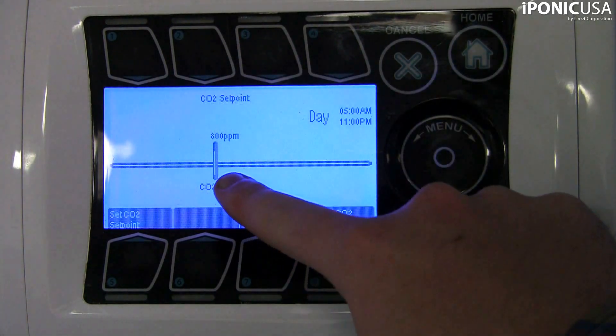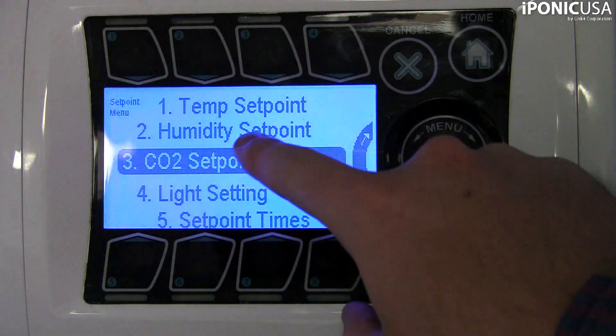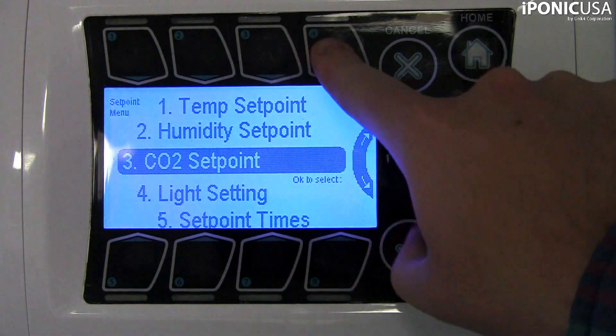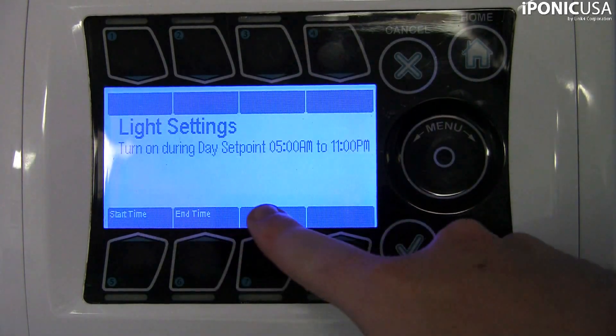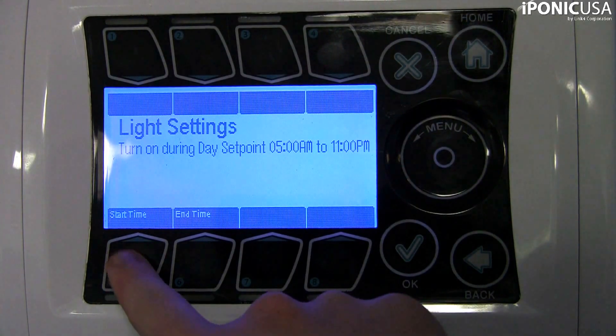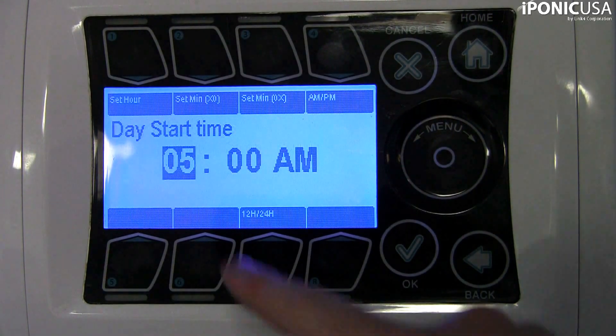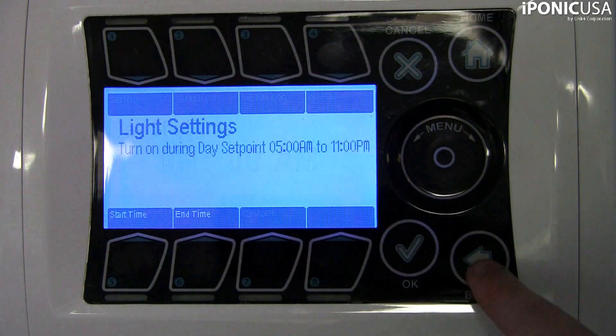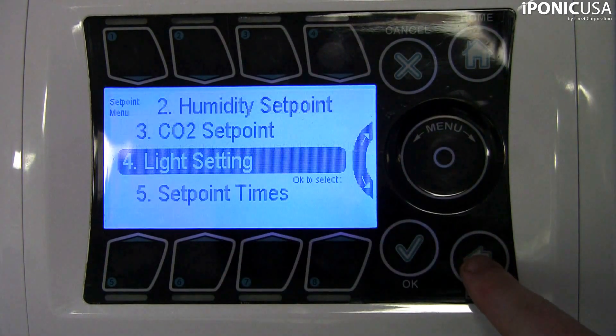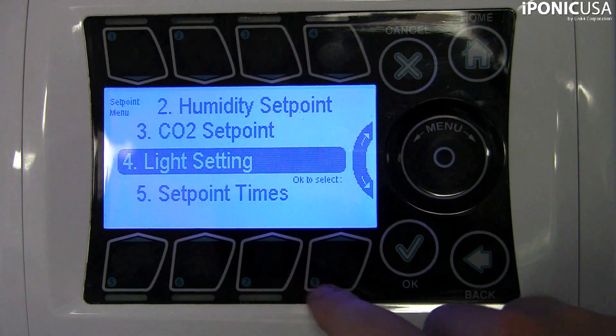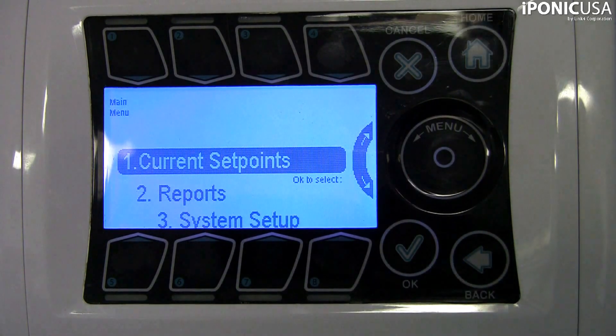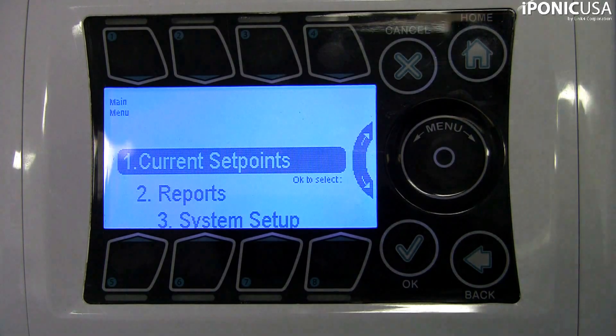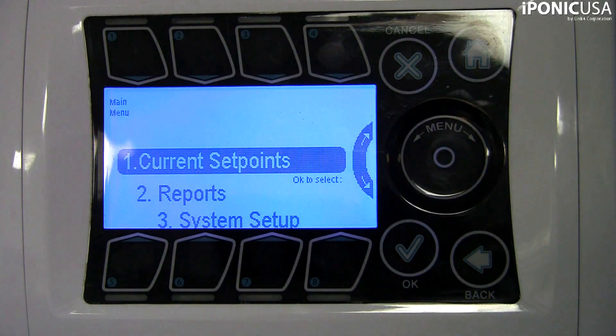The default nighttime set point begins at 11 p.m. with a normal temperature range between 65 and 85 degrees Fahrenheit. The humidity target range is between 40% and 60%, the CO2 target is set to off or zero ppm, and the lighting equipment is also set to off.